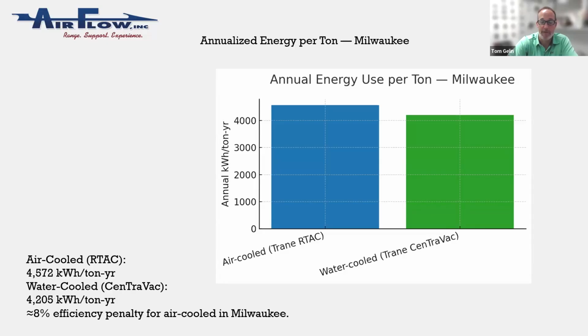And if you have a constant load, you use a water-side economizer, maybe that's not so bad. This isn't a great representation, but I used the tools available to me since I'm not doing a full analysis. What's fun is I asked a handful of people, hey, when do you switch to water-cooled? They said, I don't know. I asked someone in the office, because generally as a consulting engineer or contractor you're not paid to do a full analysis of air-cooled versus water-cooled. So all I'm sharing here is that maybe the penalty for air-cooled isn't so bad, and certainly the complexity goes way down without that cooling tower.